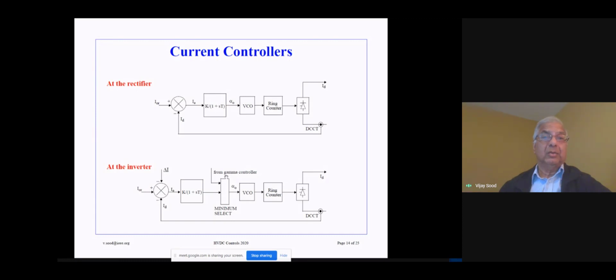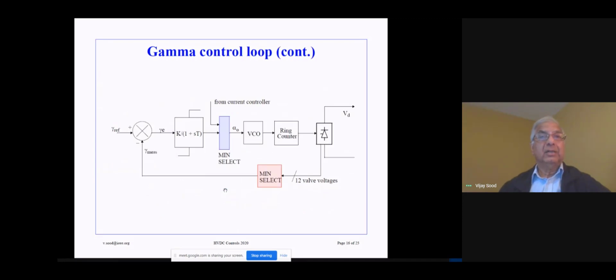So this gamma controller is shown next. Over here, this is the gamma controller. So you can see that we have a gamma reference setting. We measure the gamma. To measure the gamma, we have to have the valve voltages monitored. We select the minimum of the 12 valve voltages in a 12 pulse bridge, for instance. This is a min select circuit, so we want to make sure that the minimum gamma is selected. We compare these two values. We generate a gamma error signal. We go through a PI regulator and then into the current controller, which comes from the other side. So this is the gamma controller.